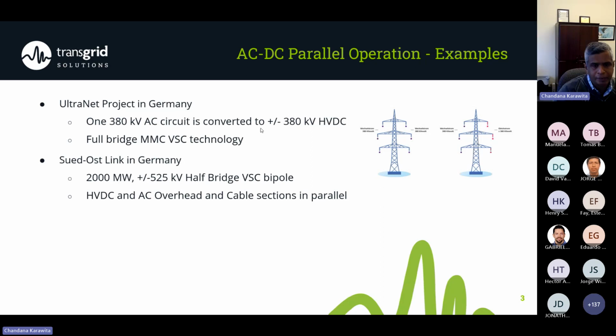And this is actually a unique application. They decided to convert one of the circuits of a double circuit 380 kV transmission tower. You can see this double circuit transmission tower, one side was converted to DC, the other side is AC. So that means we have to operate 380 kV AC in parallel with plus minus 380 kV DC.